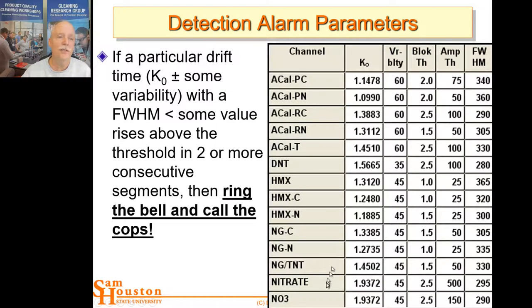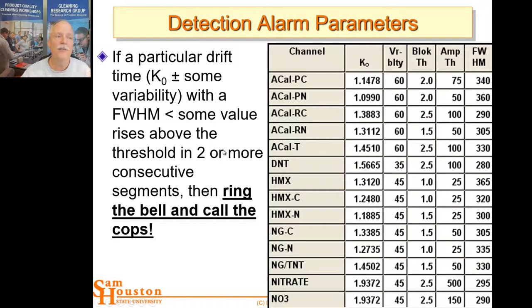These are the drift times used to detect different types of explosives, with uncertainties associated with each. If a particular drift time — plus or minus some variability — shows up with a full-width at half-maximum that meets the set criterion and appears in two or more consecutive segments (meaning it wasn't just a glitch), then you can trigger an alarm and call security because you've detected that explosive.